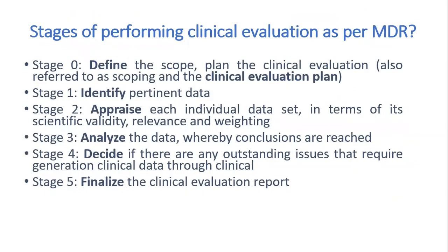Okay. And what are the stages of clinical evaluation as per MDR? We have different stages. We define the scope, that is, we first make a clinical evaluation plan where we put our requirements, and then we identify the pertinent data. After identifying the data, we appraise the data based on the weightage of scientific validity. After appraisal, we analyze the data, wherein we summarize the conclusions.